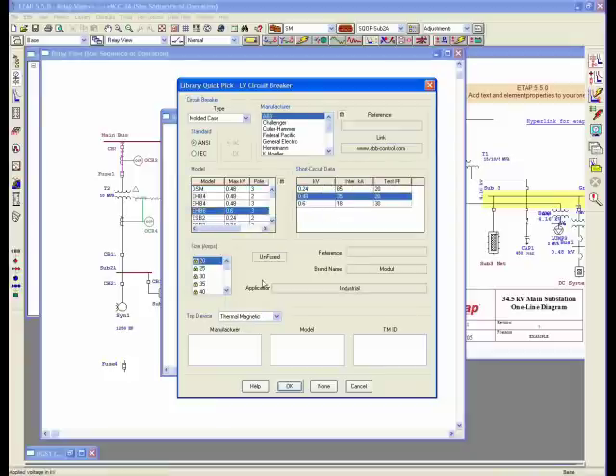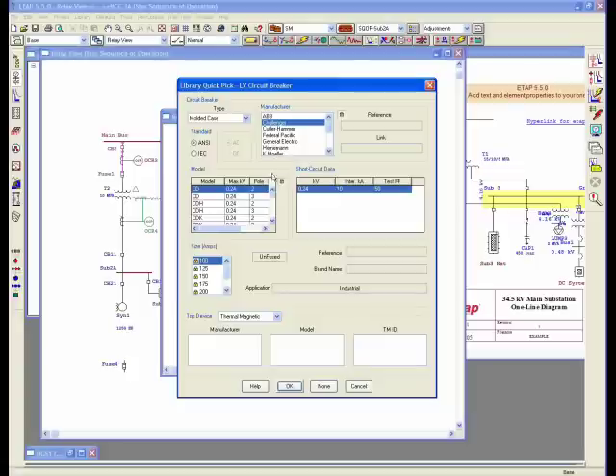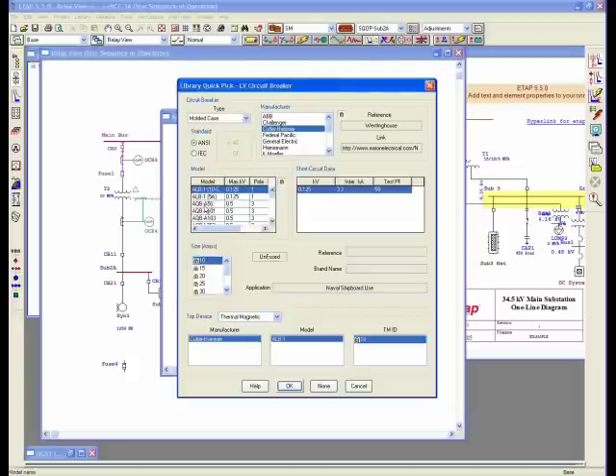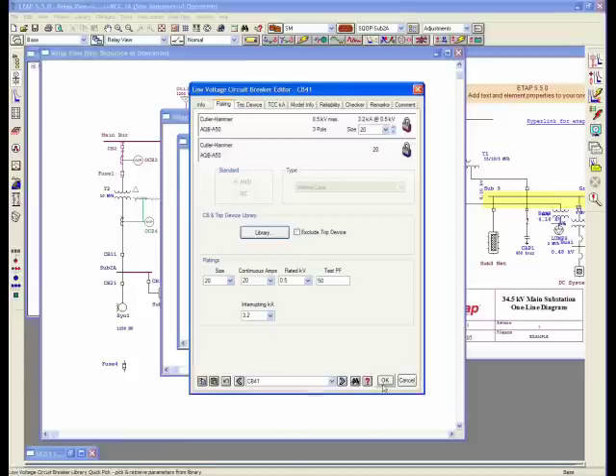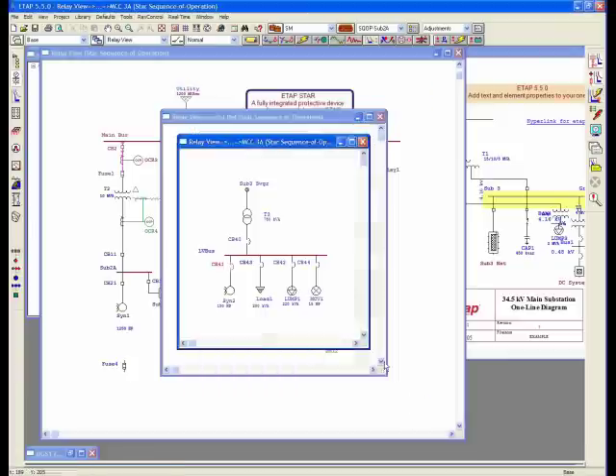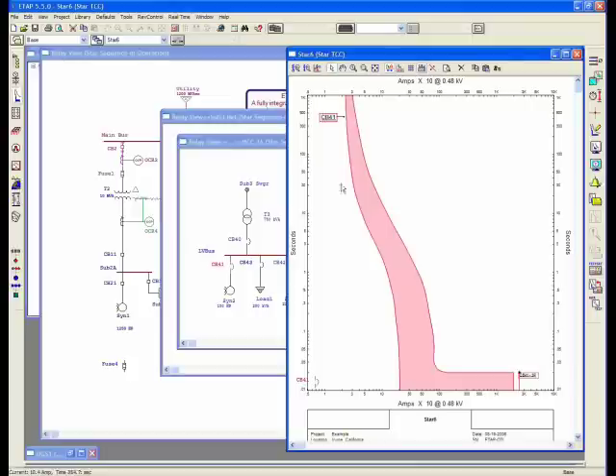So I can select this type, and it has a Cutler Hammer AQB trip device. Basically, it has the trip setting which is not fixed because it's a thermal device, and I can simply plot that device. It's the device you see here.